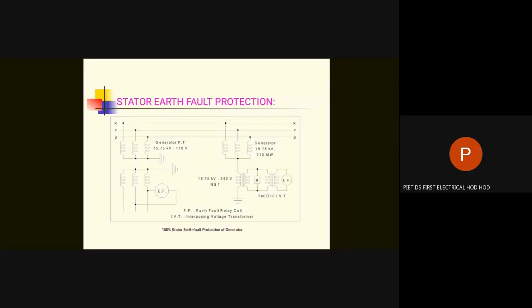In stator earth fault protection, if an external fault occurs and the line CT gets saturated, then the system may malfunction. How can we provide protection against that? Stator earth fault for external earth fault. In stator earth fault protection, if an external fault occurs, then the line CT gets saturated, so the system may malfunction.